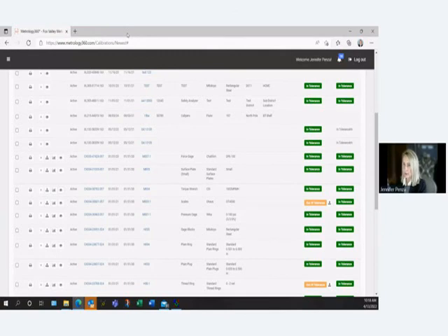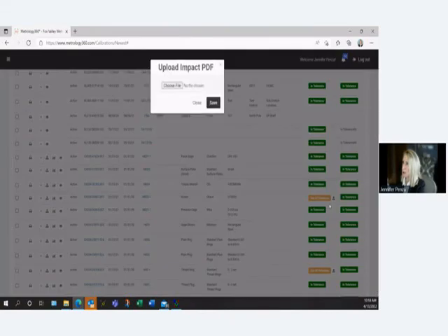The other interesting thing about this review is if you're reviewing an out of tolerance item, or gauge rather, sometimes if it's been out of tolerance, you're going to have to do an impact statement to say whether or not this gauge affected your manufacturing process. Notice over here, out of tolerance condition, that's how we received it when we received it at Fox Valley. You have another little icon over here where you can upload an impact statement that you have and save it.